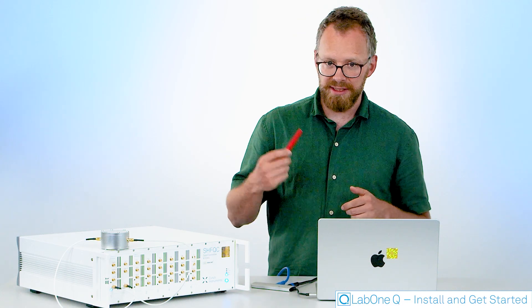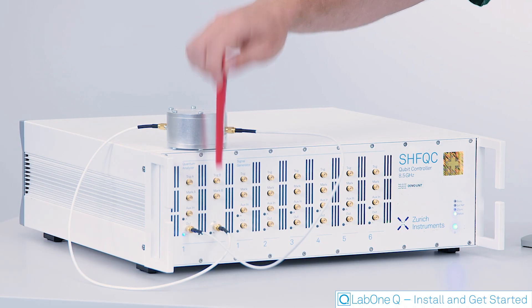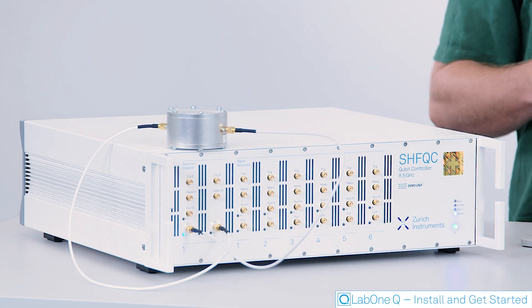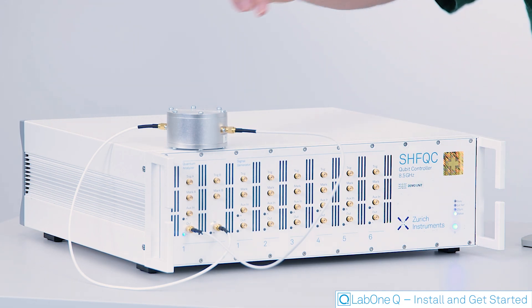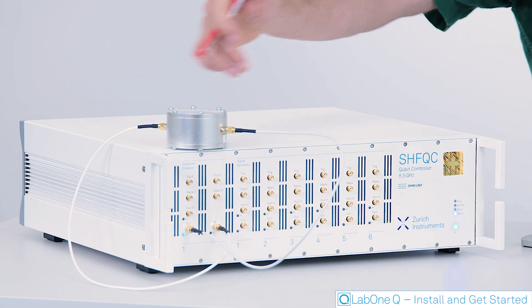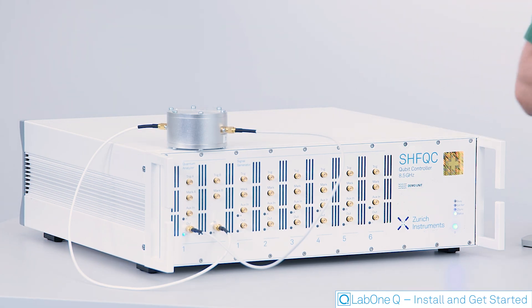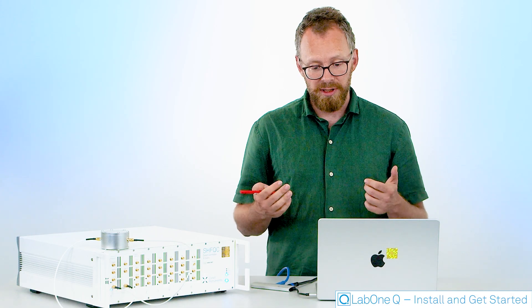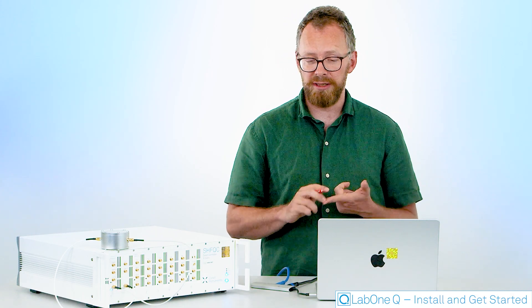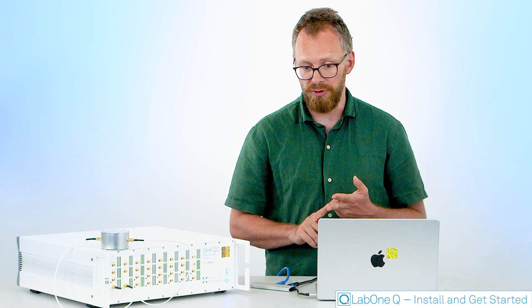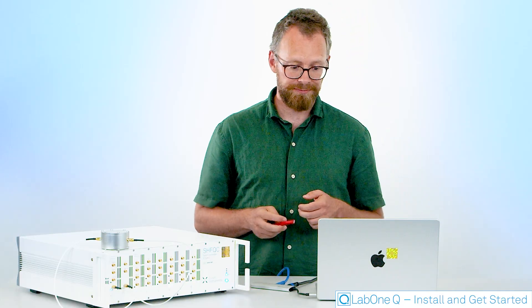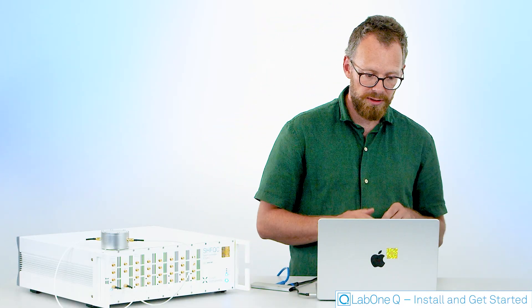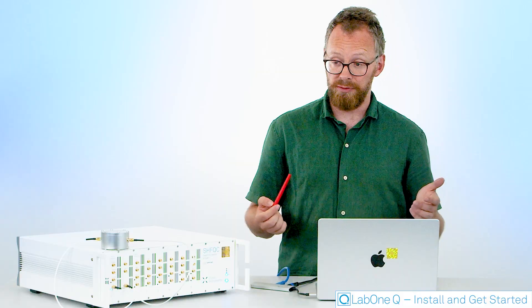In this case, I'm only going to use the quantum analyzer part of the instrument to excite this resonator at specific frequencies and then analyze the return signal at the same frequency. This example notebook is publicly available again in our GitHub or you can also download it through our manual. You will find the link below in the comments. And let's get started with the code.